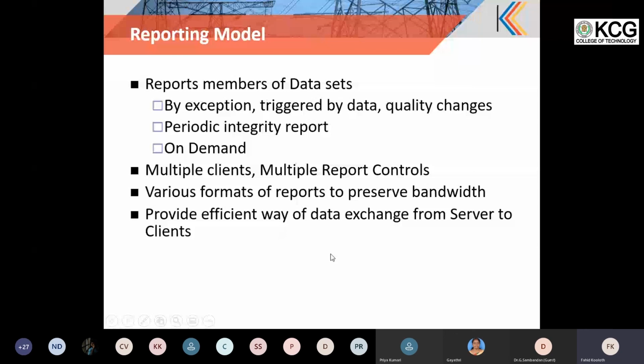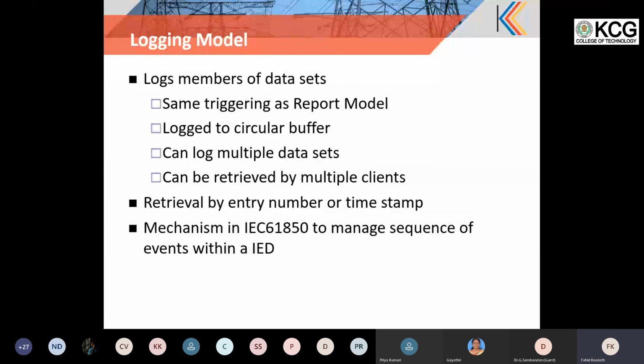Logging is a similar scenario to the report, but the major difference is that a report is automatically generated and sent out based upon the trigger condition specified. Logging, based upon the trigger condition, enters in the SOE, sequence of events buffer, and only when the client asks for that will it be sent out. That is mandatory. So this is the key representation of how logs and reports get generated.